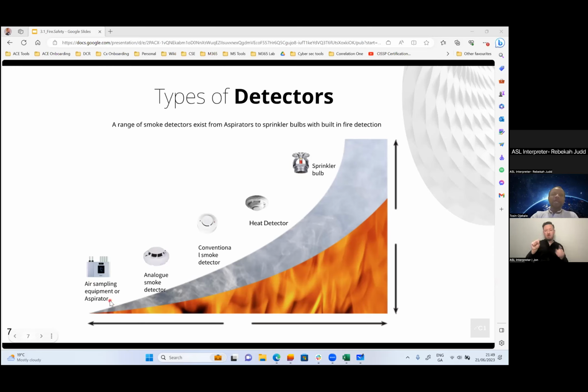So you hold it, it has a sensor that comes with it. You can go around and manually move closer to anywhere you think the smell is coming from, any of the racks. You put the detector inside of the rack, around the rack, manually like that. It will try to gauge the strength of the smoke to know where it's coming from. The more you move around, the stronger the smoke detected, so it will beep and show you where the smoke is likely coming from. That's what you do with this first one.